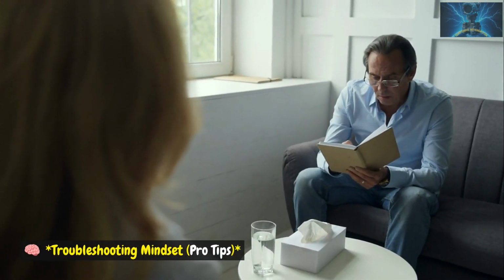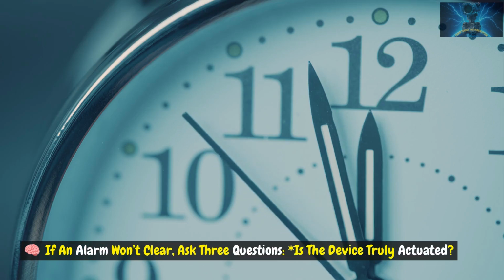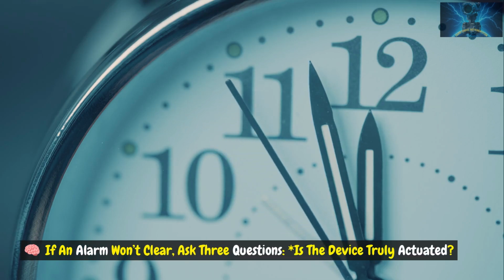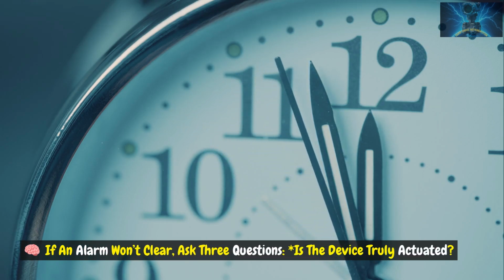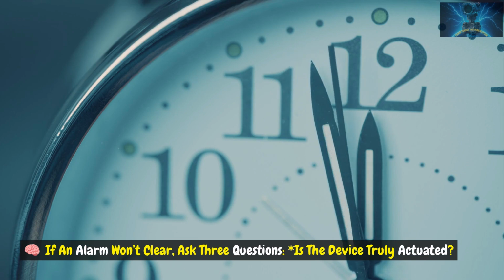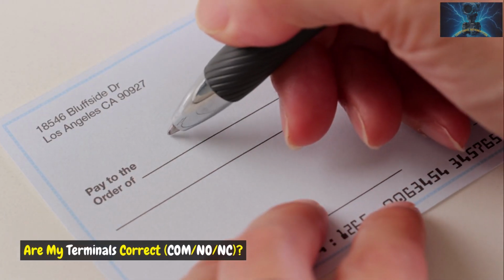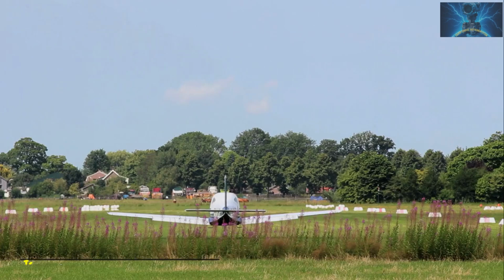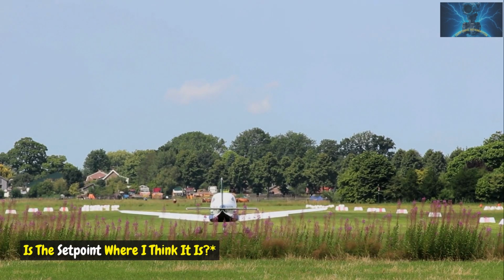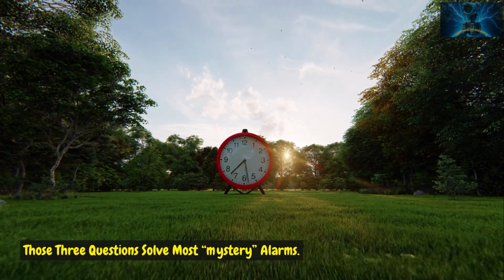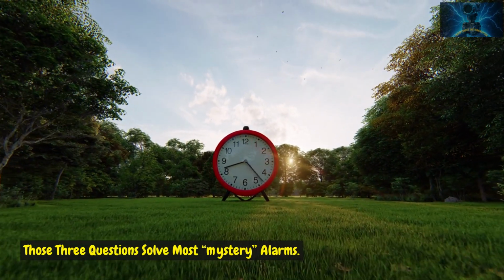Troubleshooting mindset. Pro tips. If an alarm won't clear, ask 3 questions. Is the device truly actuated? Are my terminals correct? COM, NO, NC? Is the set point where I think it is? Those 3 questions solve most mystery alarms.